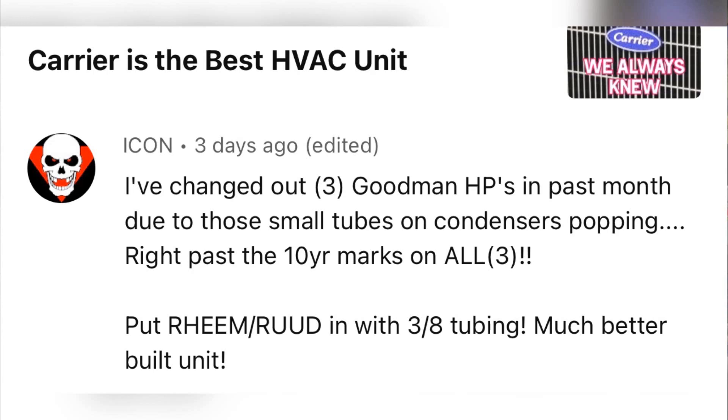I've changed out three Goodman heat pumps in the last month due to those small tubes on the condensers popping right past the 10-year marks on all three. He says to put in Rheem-Ruud with 3/8 tubing — much better built unit.